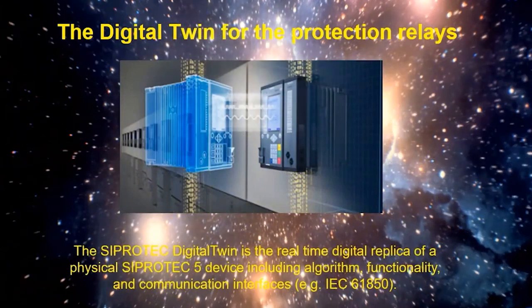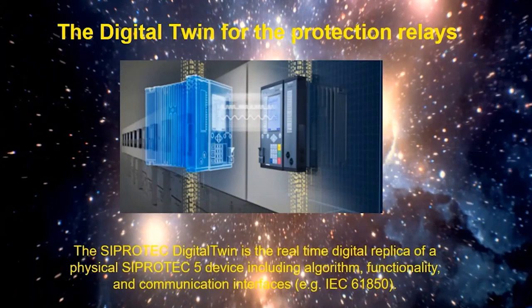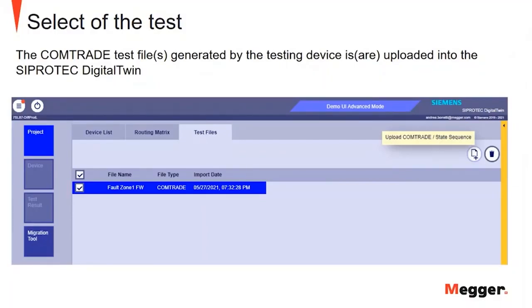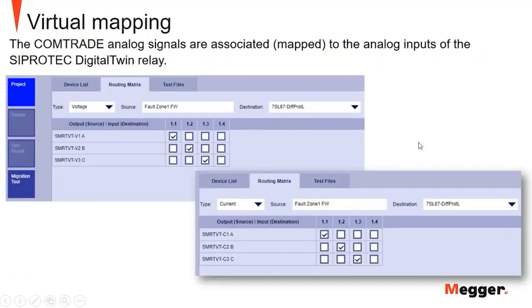We have SIPROTEC Digital Twin, which is the real-time digital replica of a physical SIPROTEC device. So the files that have been generated by the testing device are uploaded into the SIPROTEC Digital Twin environment. Upload ComTrade. When we have the ComTrade files, for each file we map the signals of the test set, which are signals in the ComTrade file, voltage A, B, and C. We connect them to the analog input of the relay, voltage analog input 1, voltage analog input 2, voltage analog input 3.